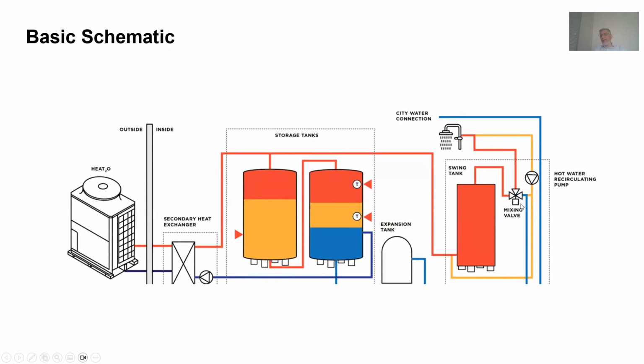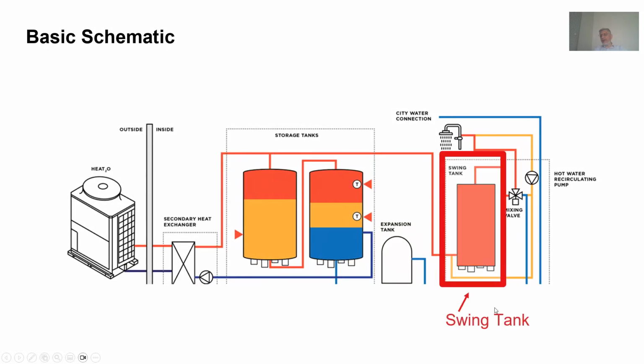To cover this, there's a swing tank that has its own electric heaters available there. So for anything coming back from the recirculation side, the electric heater will maintain the temperature set for the facility. So the electric heater in the swing tank is there to compensate or maintain the temperature that would be going to the building.